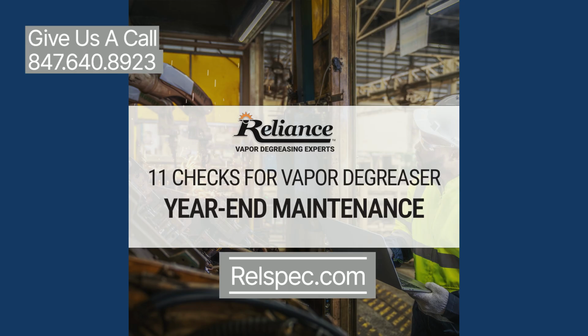Check 7. Check the interior drip gutter. Check your condensate trough, drip gutter, for the primary and sub-zero coils for debris that might block the flow out of the gutter. Check 8. Inspect your refrigeration systems. Clean your refrigeration system heat discharge coils, as they should be clean and free of oil and dust accumulations. Check the condenser to ensure that all components appear to be in good condition. Consider having a refrigeration technician visit to check the ability of the system to achieve the target temperature ranges when the vapor degreaser is in operation.